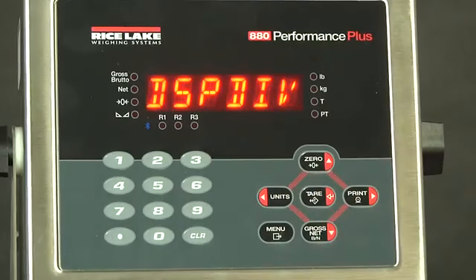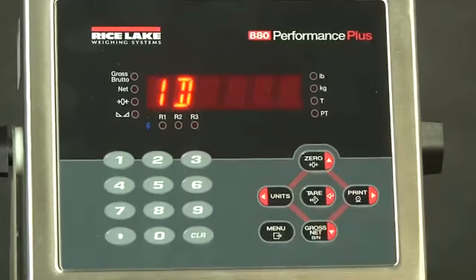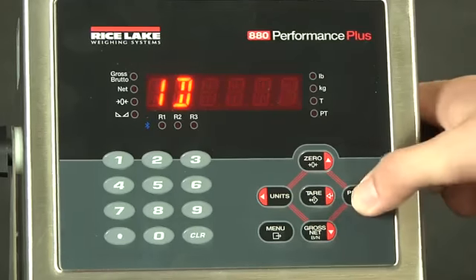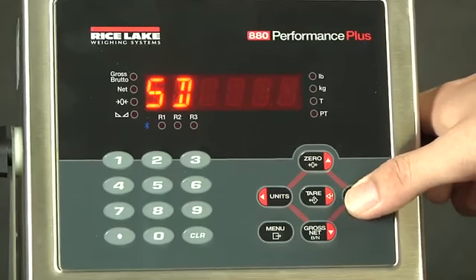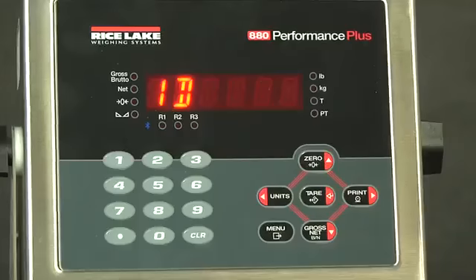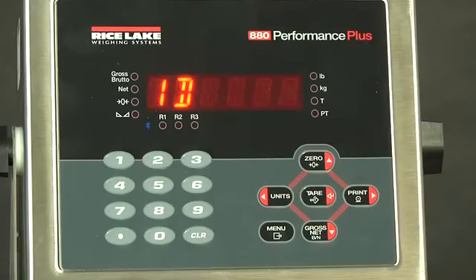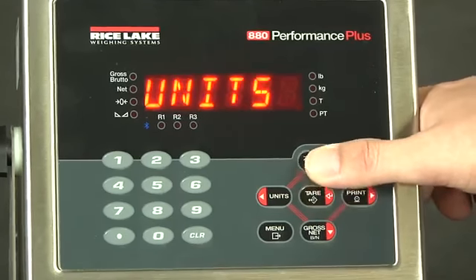The next is display divisions. If we drop down here, we have several available options. We can count by 1 division, 2 divisions, or 5 divisions. If we were setting up, say, a truck scale, we would actually use 2 divisions with a decimal point location of 0. This would give us 20 pound divisions, or whatever we happen to be using at the time for our units. With 20 pound divisions, if we're going to 120,000 pounds, it would be 6,000 graduations. The way we determine this is 120,000 divided by the 20. That is our count by, and that will give us our graduation size. So we will accept this because it is currently what we are looking for.